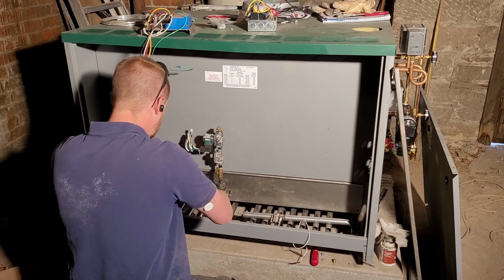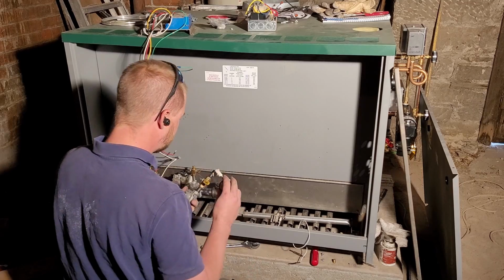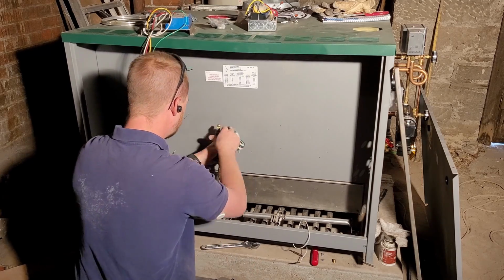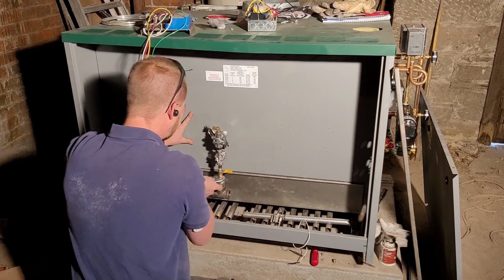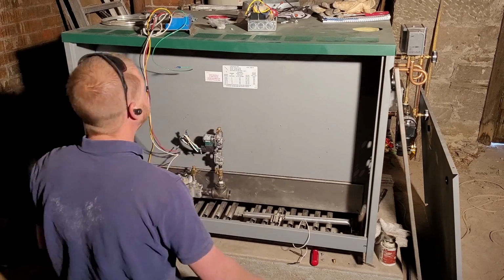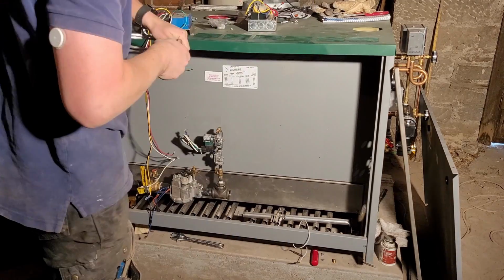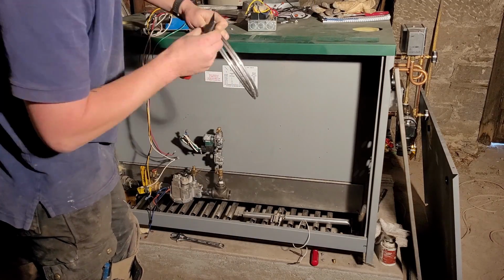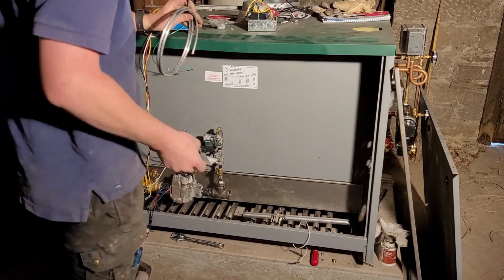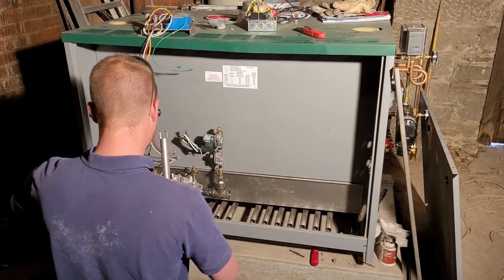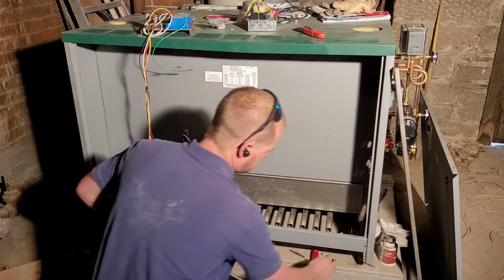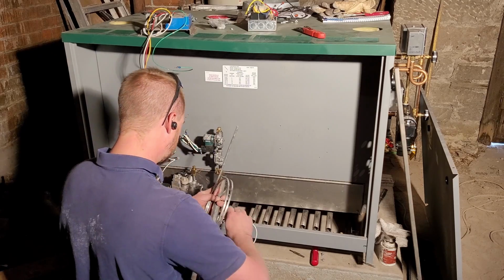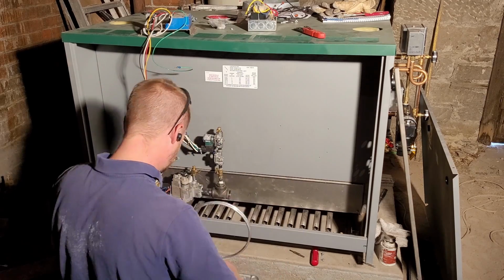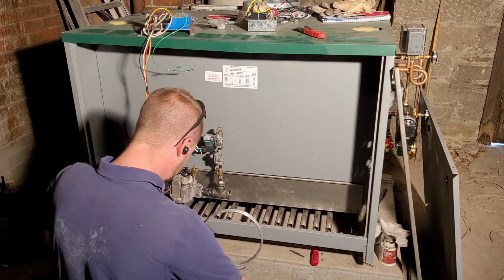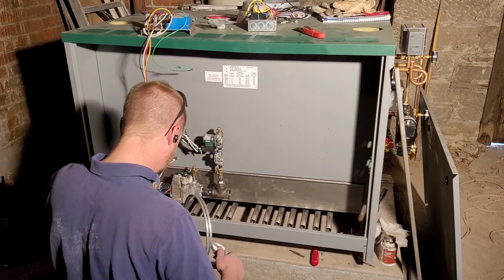And then when the boiler gets a call for heat and needs to fire, it will send power to the little sparker that exists on the pilot. And you'll see that little white wire coming off the pilot. That will ignite the pilot flame, and then there is a little sensor that determines whether or not the pilot is on. Once it proves that that pilot is on, then it will allow gas to flow through the main valve and light the burners.